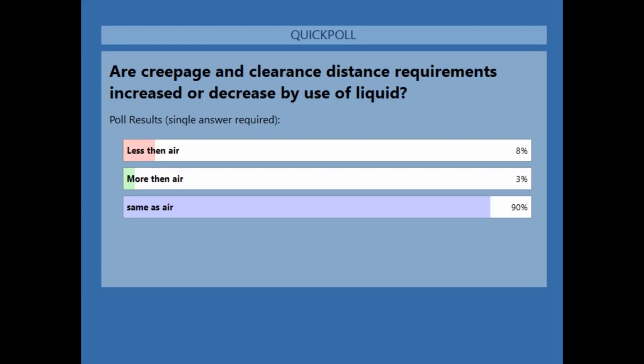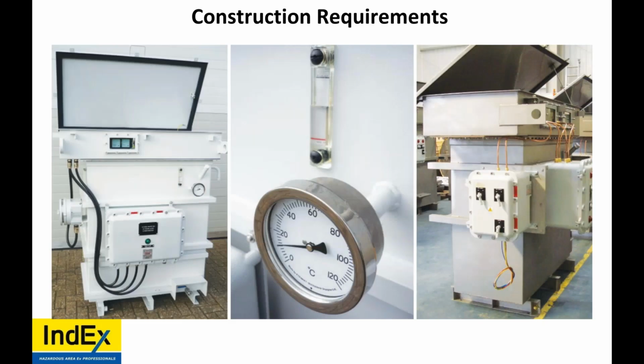Now, everybody, the answer is same as air. The oil does not reduce any requirements or give you extra protection when it comes to creepage and clearance distance requirements. Okay? The oil or liquid is for cooling, dissipation of heat produced.